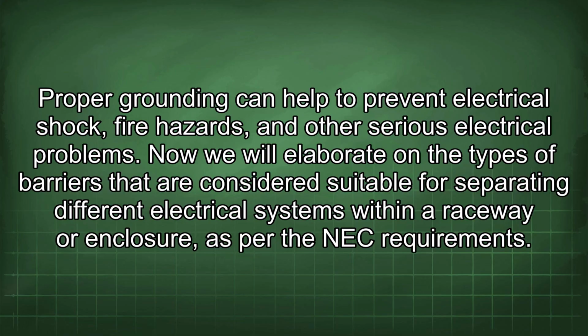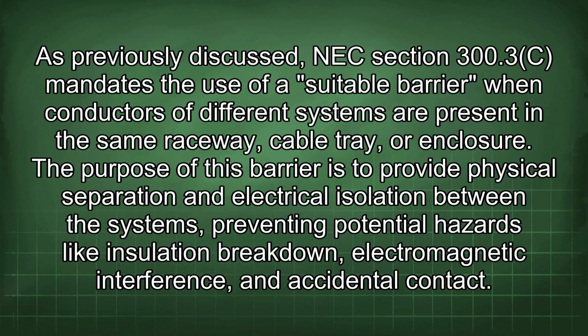Now we will elaborate on the types of barriers that are considered suitable for separating different electrical systems within a raceway or enclosure as per the NEC requirements. As previously discussed, NEC Section 300.3(c) mandates the use of a suitable barrier when conductors of different systems are present in the same raceway, cable tray, or enclosure. The purpose of this barrier is to provide physical separation and electrical isolation between the systems, preventing potential hazards like insulation breakdown, electromagnetic interference, and accidental contact.